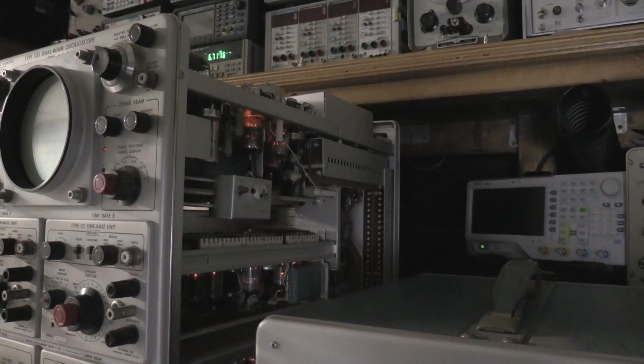And I have already checked the high voltage, both high voltage supplies, and I actually have upper and lower high voltage. What I'm not seeing is glow from the CRT. So I am starting to think my filaments might be dead in the CRT, which, if that is the case, is going to be a terminal failure of the unit.